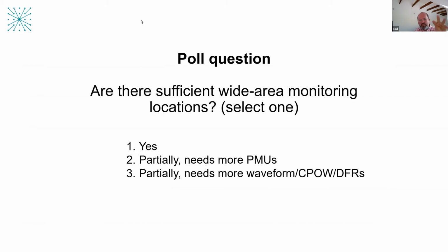So getting that granular detail and being able to trace back the issue to its source is very important, because otherwise you're only looking at an aggregated view of the grid connection from what is effectively 10 to 130 generator points. So I think it's critical to do both of these things. Everyone would love more affordable visibility that's dependable and reliable and fast, but you also need that greater detail and better sampling rates to be able to get the underlying issues identified and not the aliased kind of high level presentation seen.